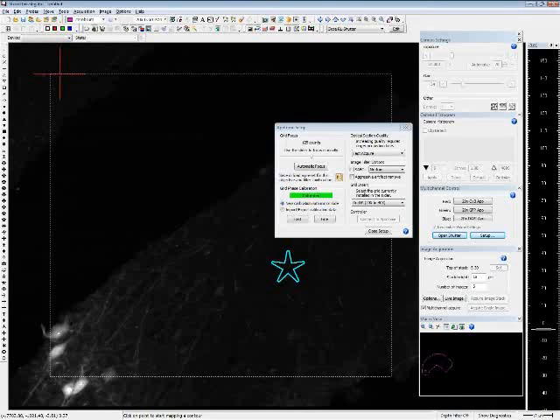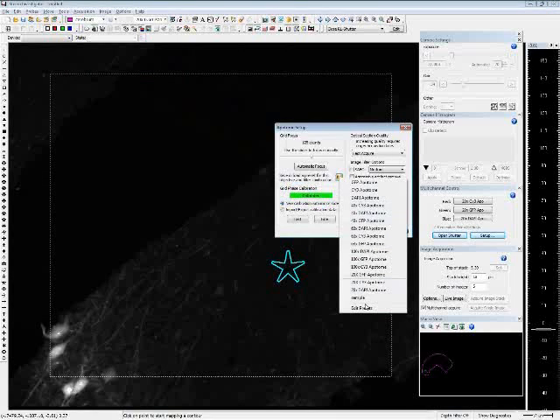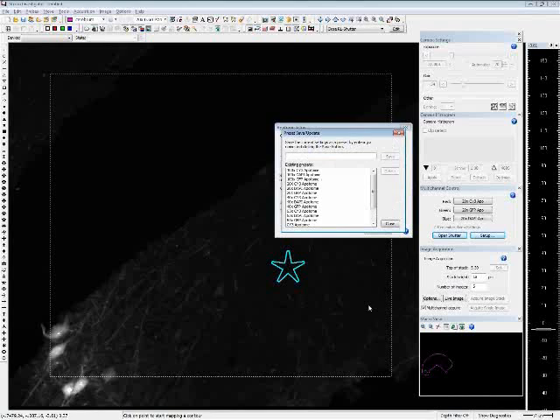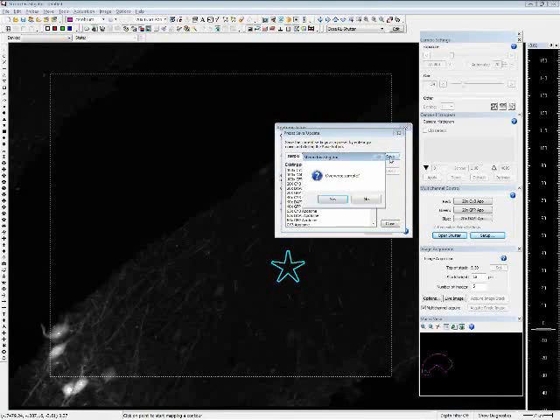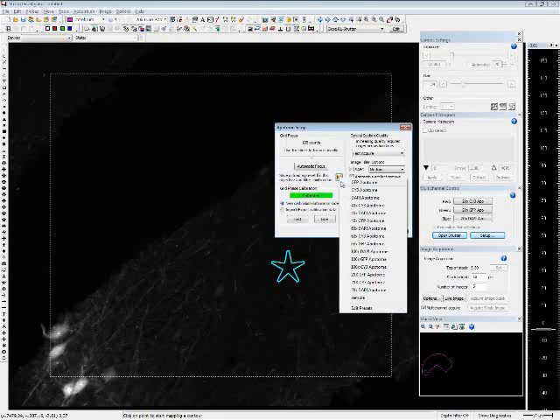I am happy with this grid focus position, so I will save it to my collection for use later in device command sequences. Click on the cabinet button, click Edit Presets, and you can save this grid focus position by typing in a name appropriate for your objective and filter combination, then click Save. This system is calibrated — in our cabinet we have a full set of objective, filter, and grid focus combinations saved for future use.